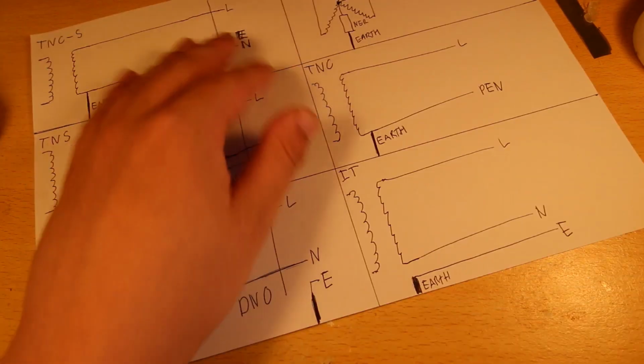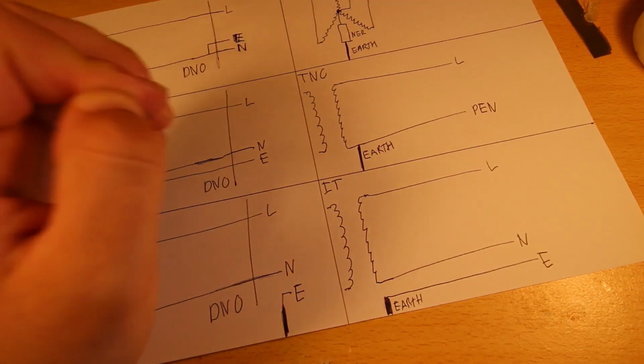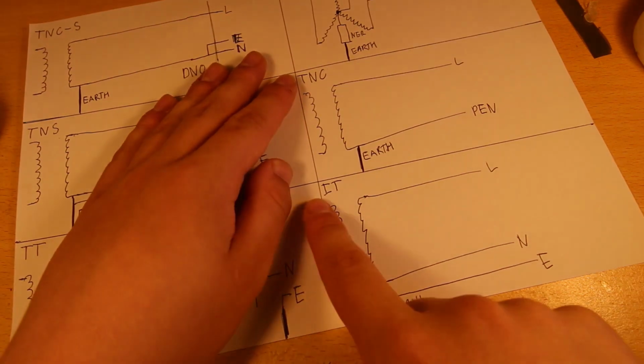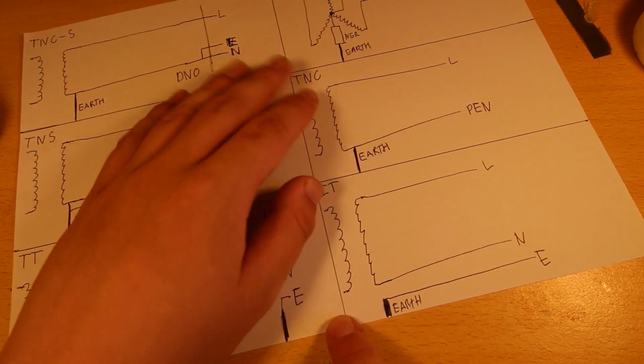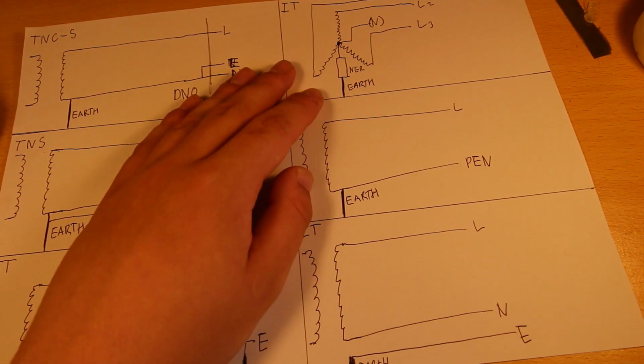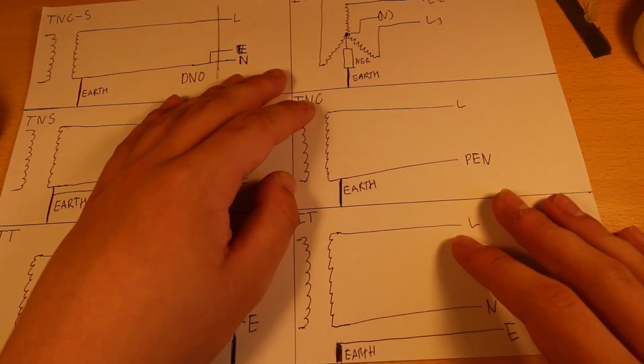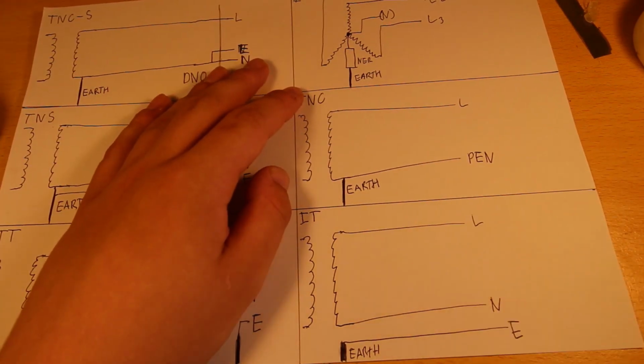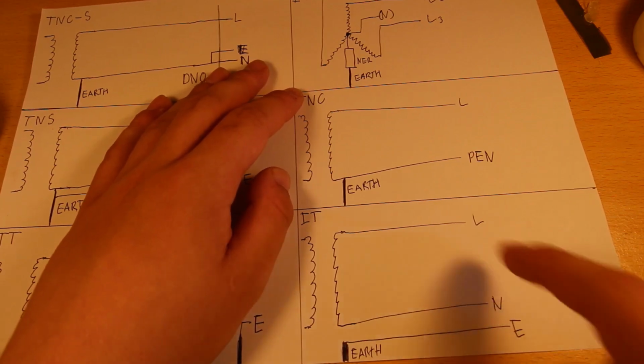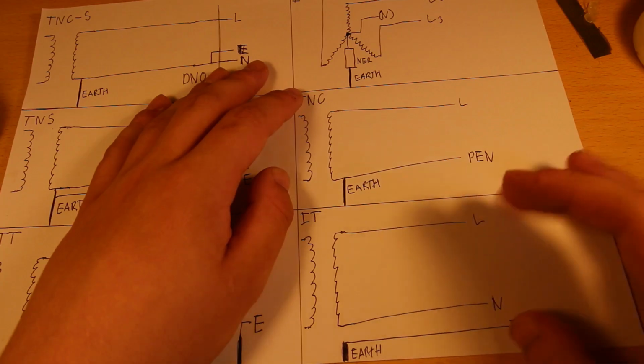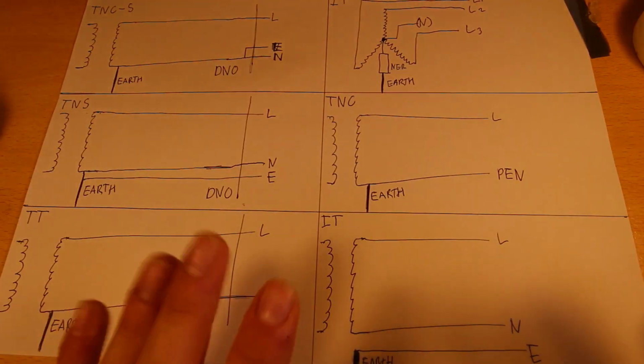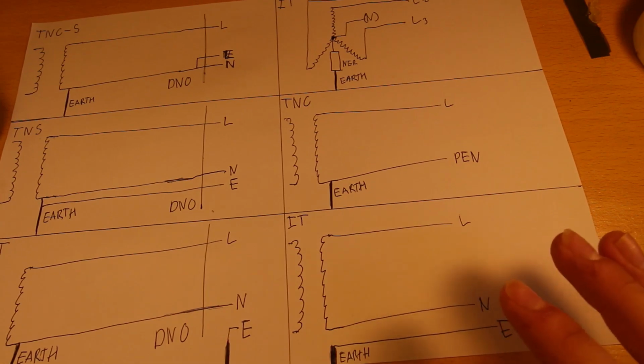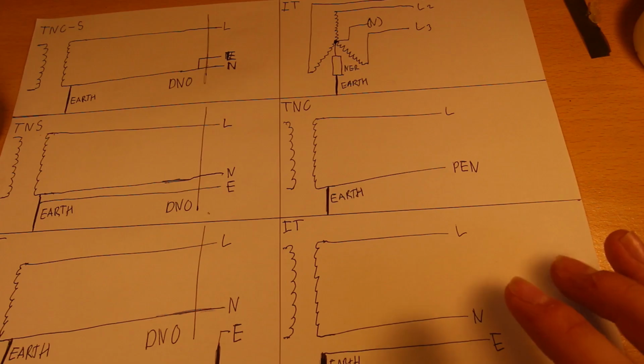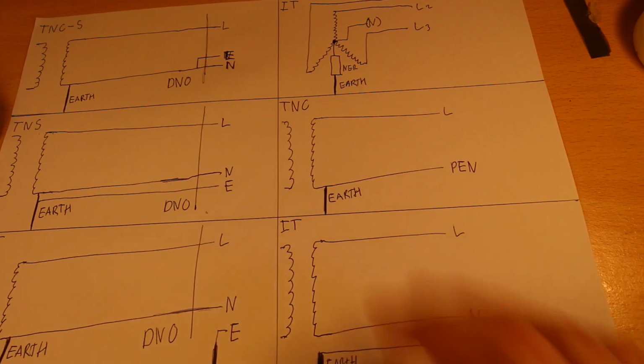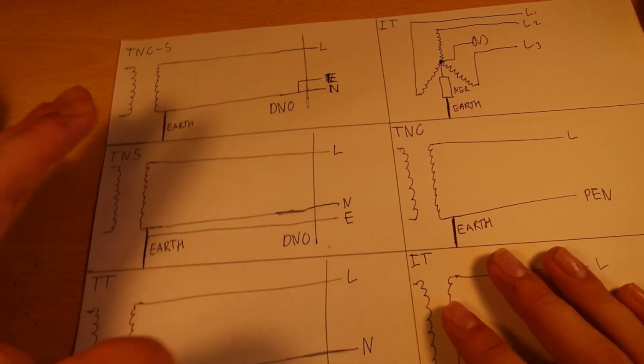neutral coming from there. The other option is terra neutral isolate, or sorry, earth isolated, which is again we have the 11 kV, the secondary is not earthed at all, so we have a live and a neutral which come out. I'm not sure how you'd term them both, because it's not really a neutral because it's not at earth potential, but you have a live and neutral coming out, and you then have an earth which is provided separately, and the live is not referenced to the earth, so the voltage between them is not tied. The IT system, the only place I can think of it being used is in operating rooms in hospitals. Other than that, I can't think of anywhere you would actually see it. So these are the 3 ones we will be focusing on today.